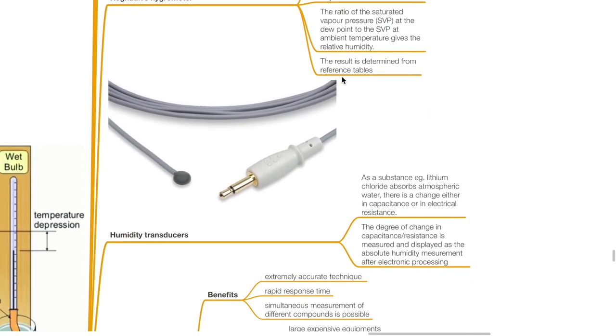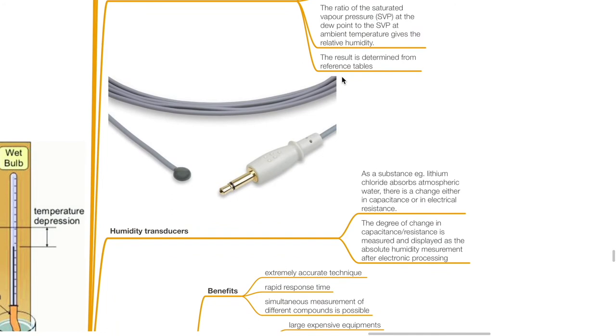Humidity transducers. As a substance such as lithium chloride absorbs atmospheric water, there is a change in either capacitance or electrical resistance. The degree of change in capacitance or resistance is measured and displayed as an absolute humidity measurement after electronic processing.